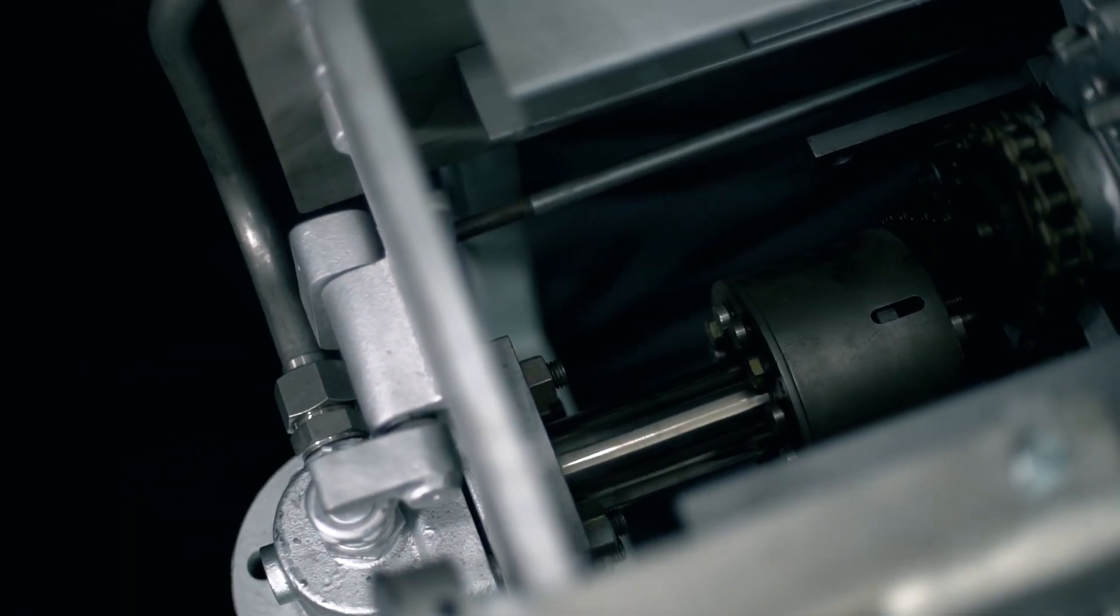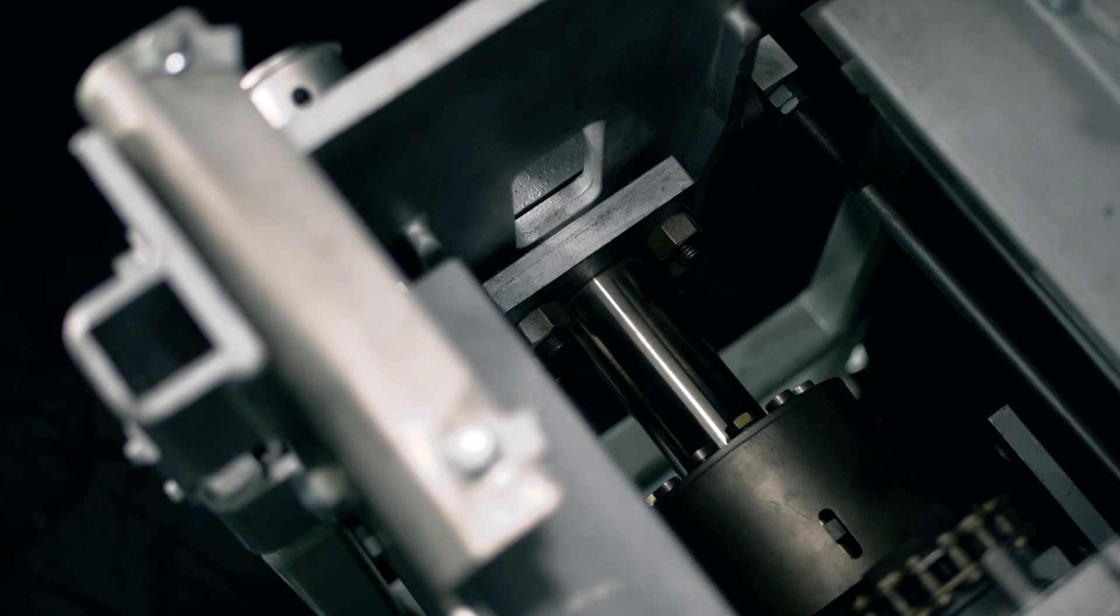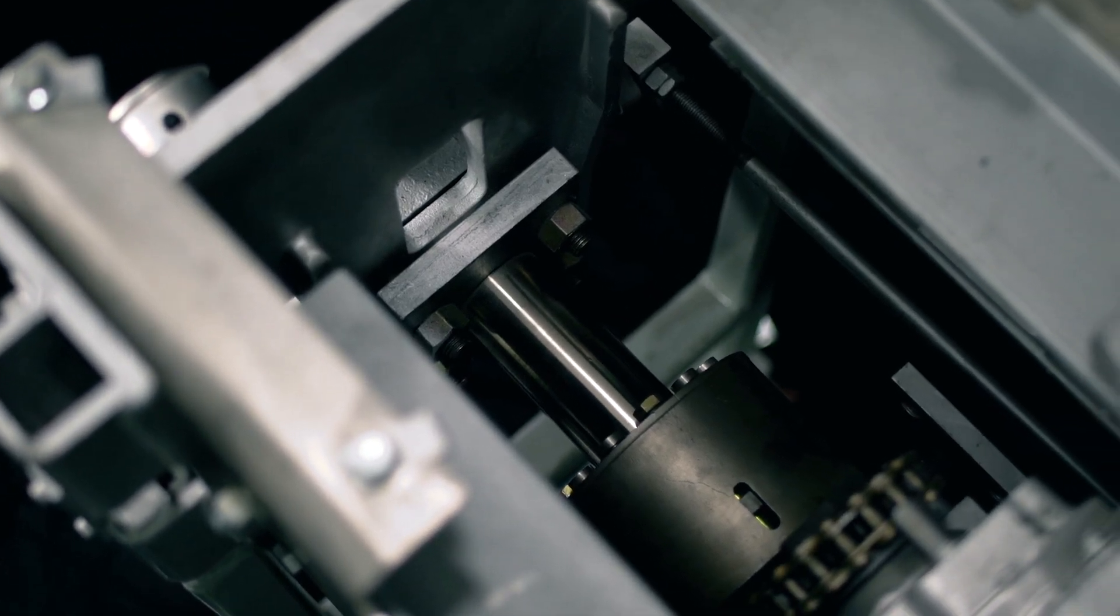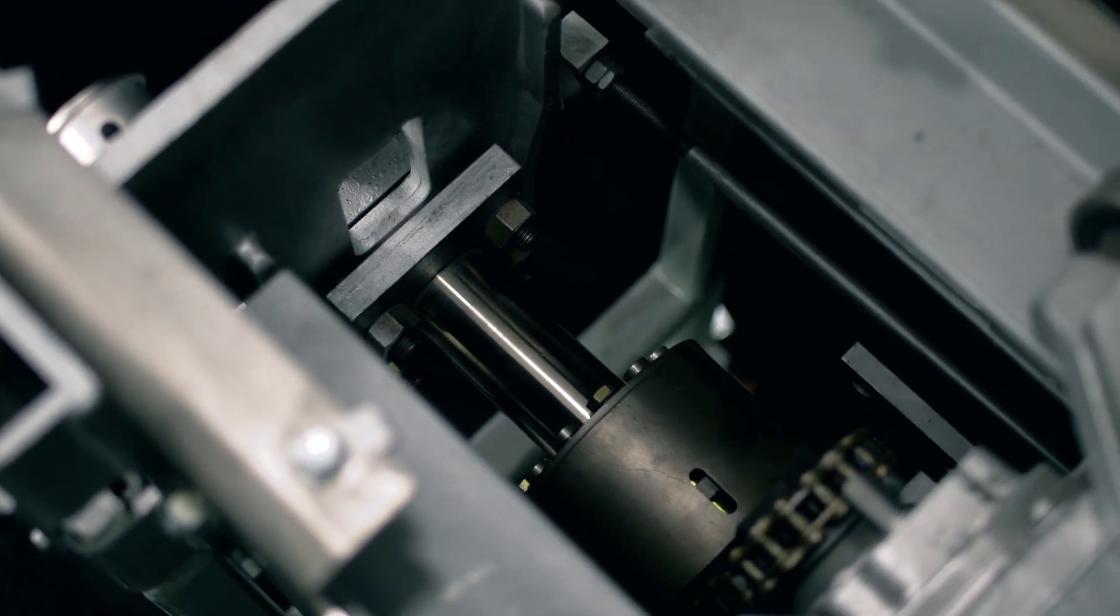Because the poppet valve regulates steam into the feed tube, you need to look out for any leaks of steam at the entrance of the feed tube.